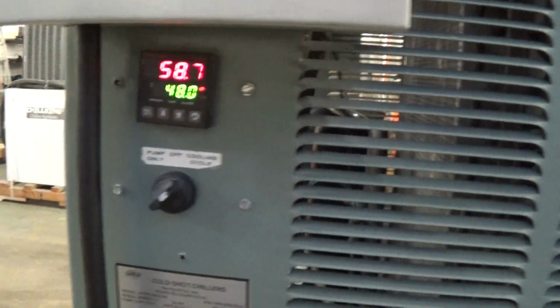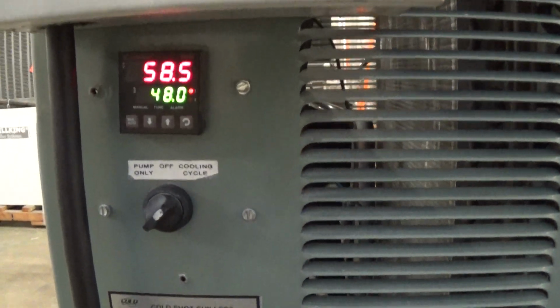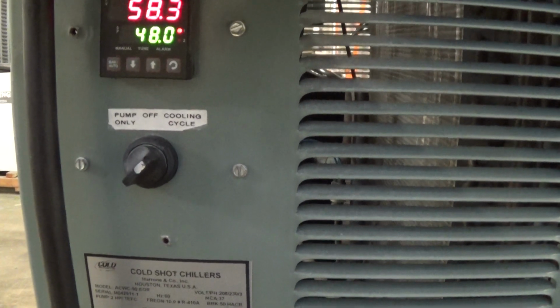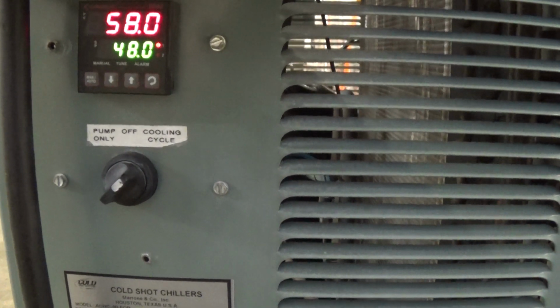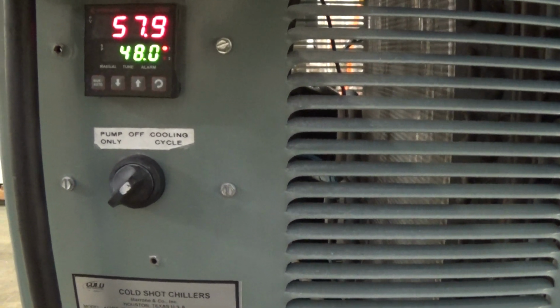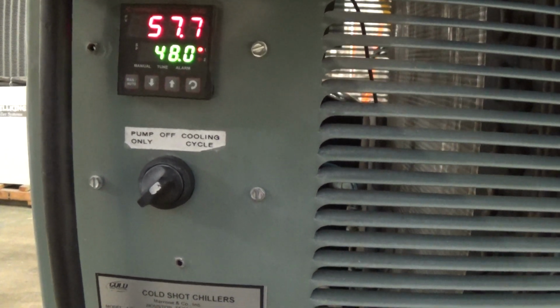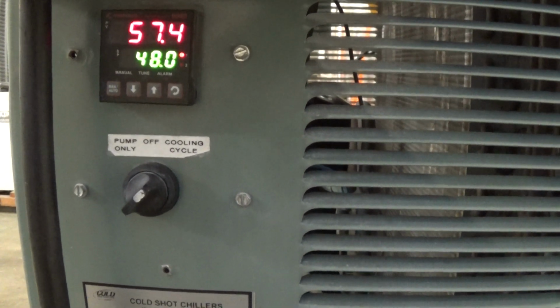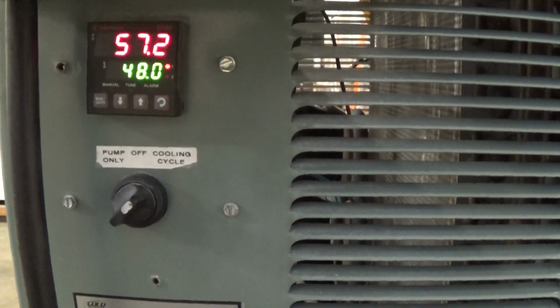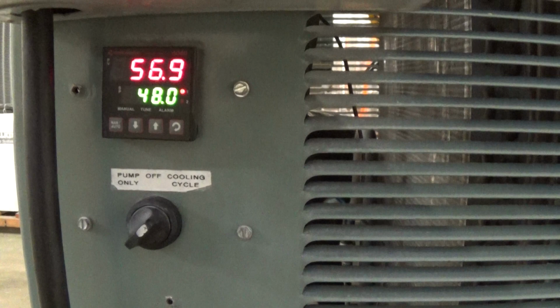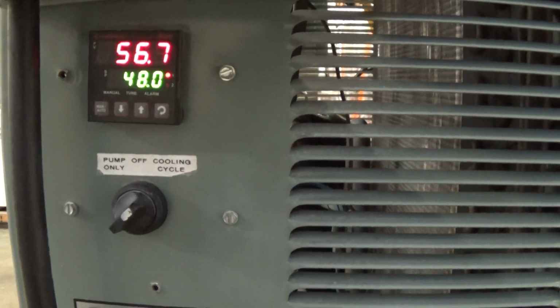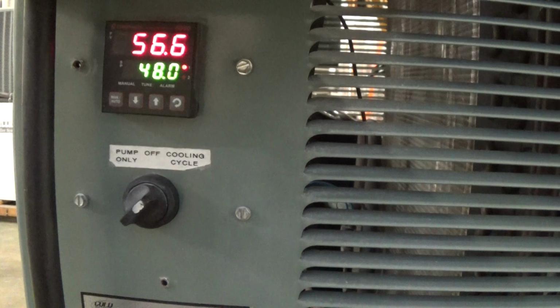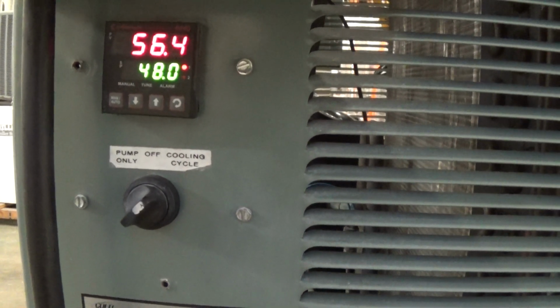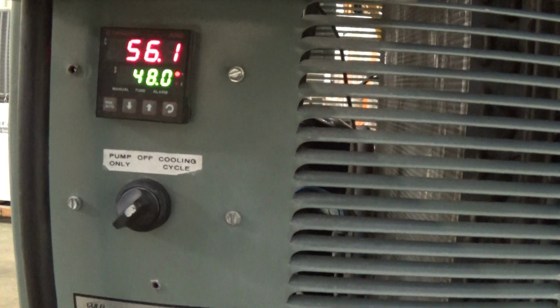Built into the controls is a differential, which is on every chiller. So if we set this at 48, it's probably going to stop at 46, and it's probably going to drift a little bit, and then the compressor is going to turn back on at about 52. So a bandwidth, if you will, or a differential of a little over 4 degrees, and that's typical. You need that to prevent short cycling of your chiller. You can see right now we're approaching 56 degrees.